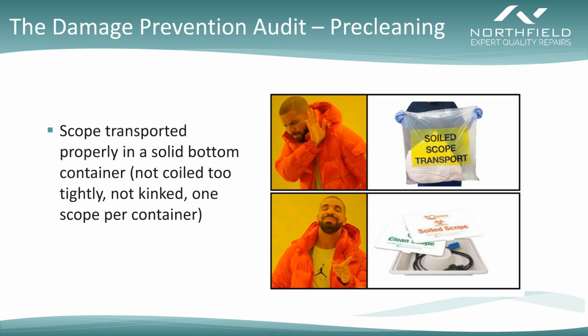By far the best practice for preventing damage to scopes is a rigid bottom container that gives the scope some support. I really like this example in the bottom right-hand corner, because this facility has even left their sponge from the pre-cleaning on the distal tip during transport, just to give a little extra cushioning in case something bumps into it. That's not required by any means, but I think it's a good idea because it helps prevent damage to that very vulnerable distal tip, which is also the most expensive area of the scope. So anything you can do to protect that is going to be beneficial.